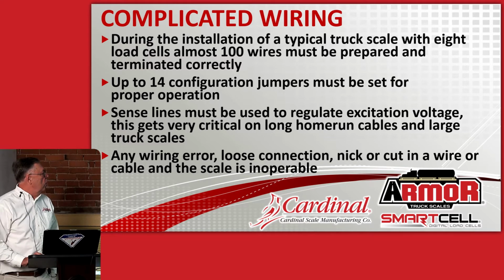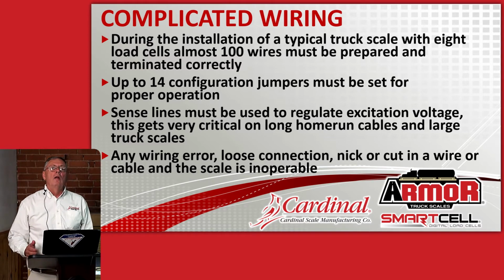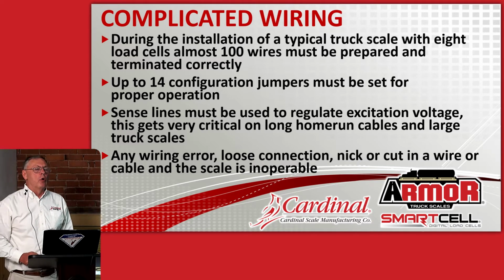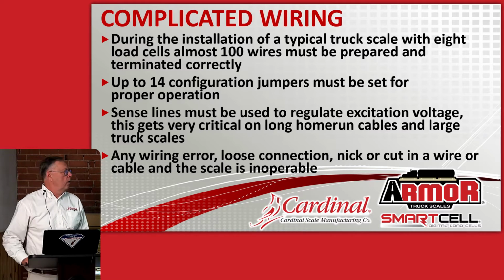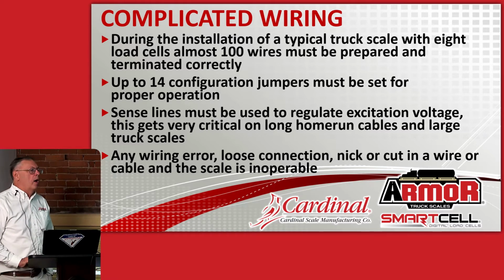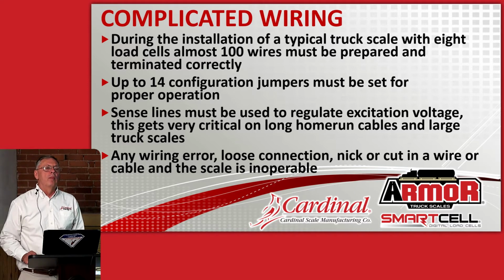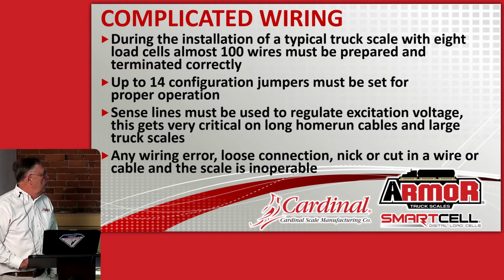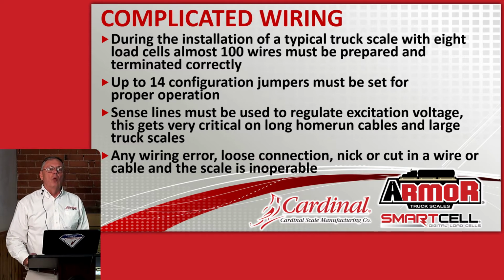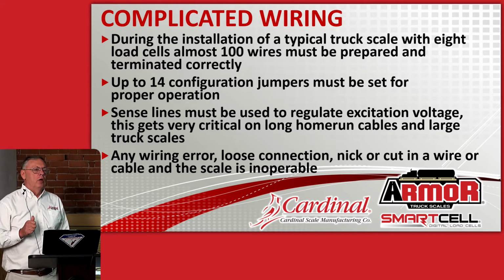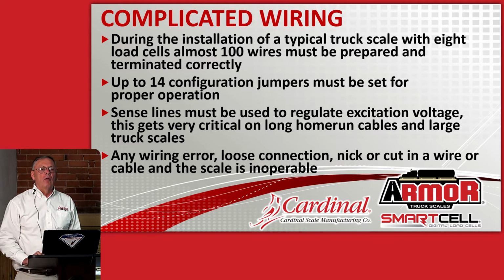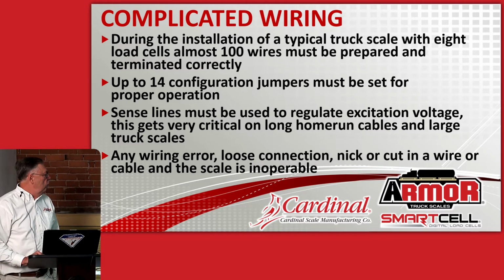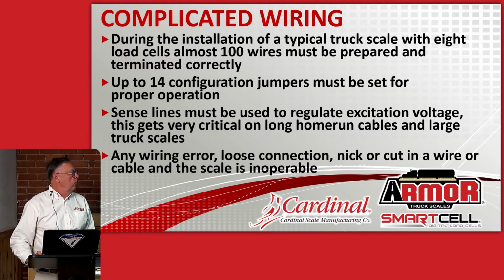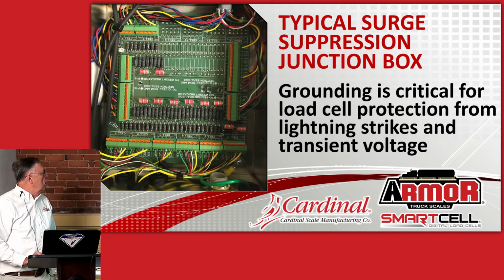On newer electronic truck scales, there's a lot of complicated wiring. In a standard 70-foot truck scale, there are almost 100 electrical connections that have to be made correctly and terminated correctly for that scale to work. We've got up to 14 configuration jumpers that have to be set correctly for the scale to work. On a standard analog truck scale, we've got sense lines that are required to keep the excitation voltage correct, depending on how far the scale is from the digital indicator. It gets to be very hard to do sometimes. And with all of these things, any loose wire or a connection out of place and your scale doesn't work.